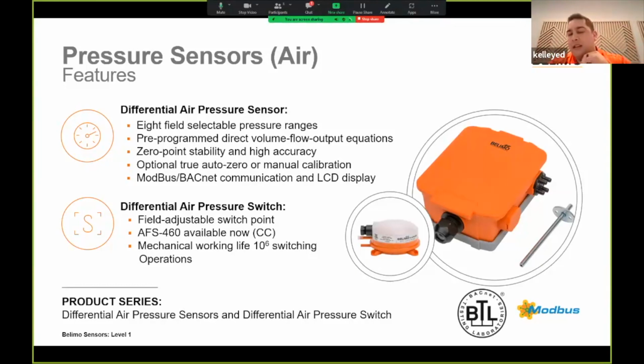Here at Belimo, again, ease of installation and commissioning also includes maintenance-free features, similar to the CO2 device that's constantly combating drift. In the pressure range, we have what we call true auto zero. If you opt in for the true auto zero version, every 10 minutes for the entirety of the sensor's life, it automatically zeros itself out. So you don't have to physically go to the sensor and hit the button. It does it by itself every 10 minutes.